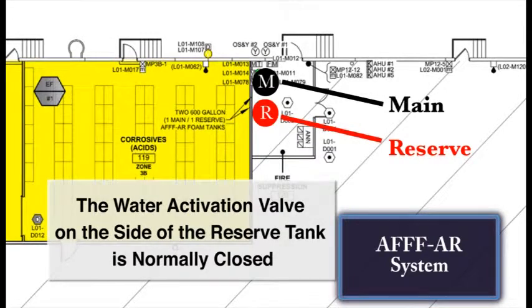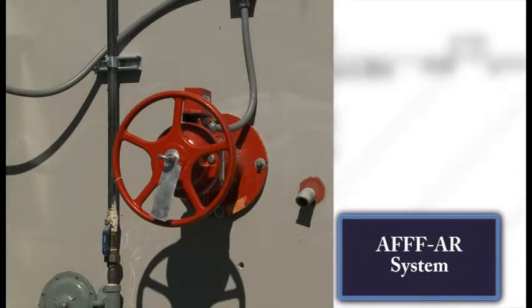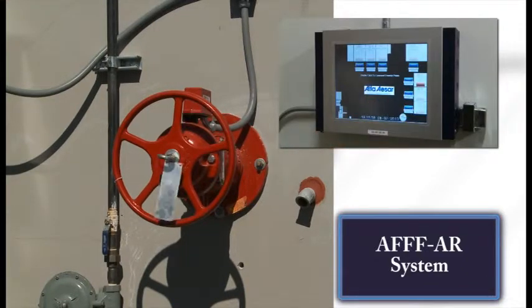The water activation valve on the side of the reserve tank is normally left in the closed position. In order to place this reserve AFFF-AR tank into service, the water and concentrate supply valves must be opened manually. The AFFF-AR system water supply for the flammable liquid storage space is arranged to allow the water supply to be shut off for the space with the use of outside stem and yoke (OS and Y) valves that can be remotely operated from inside the foam room.